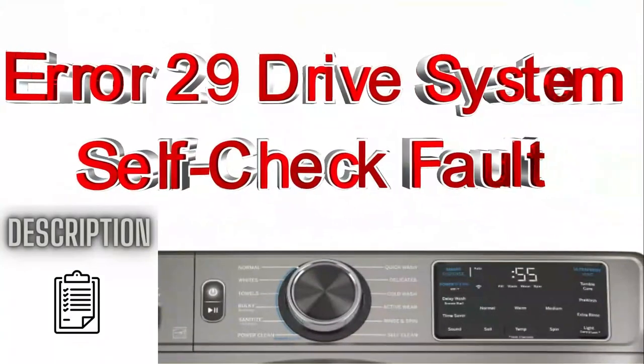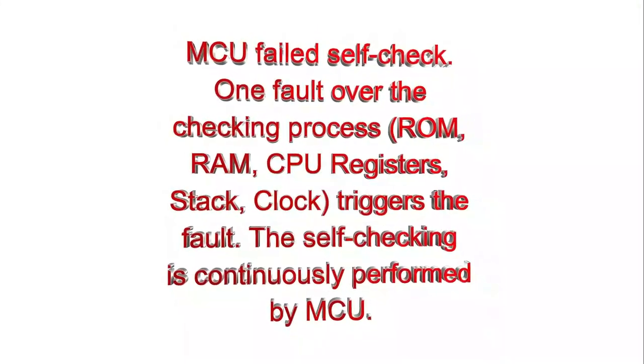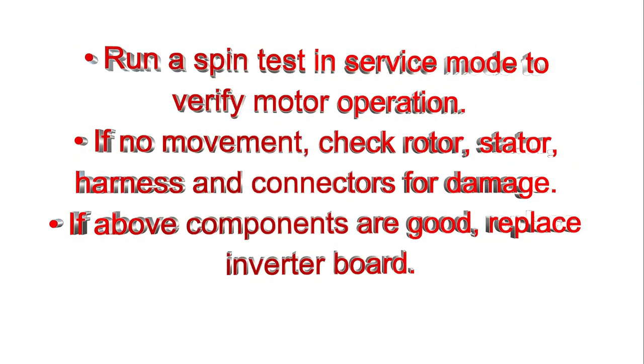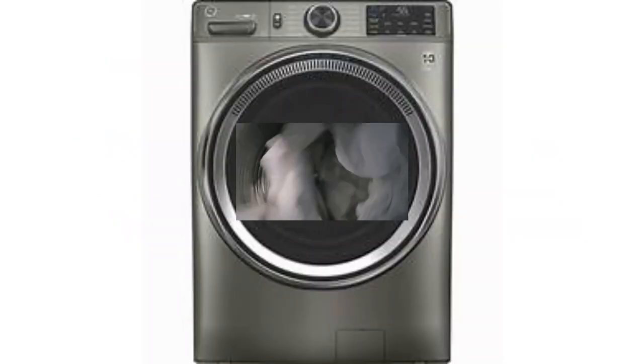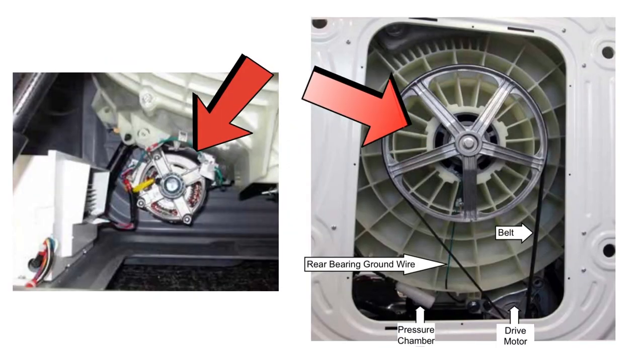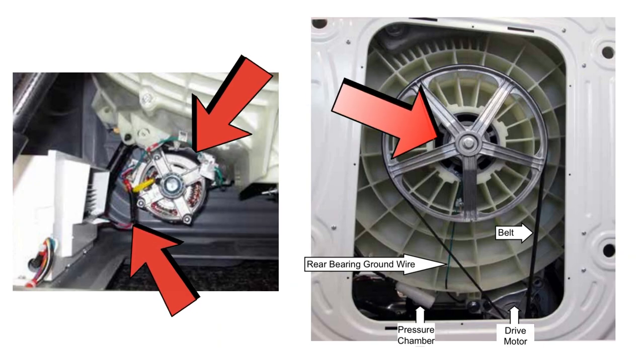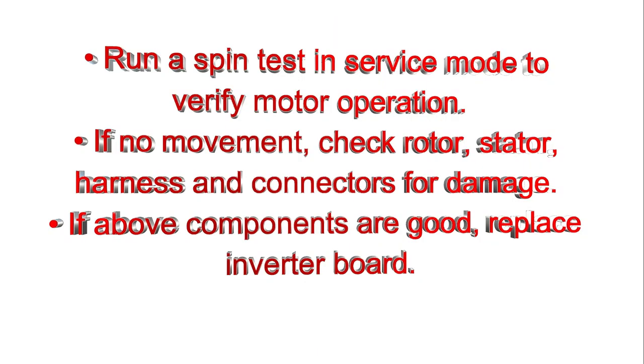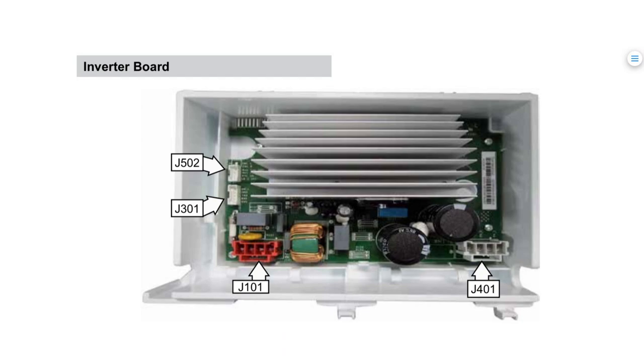Error 29, drive system self-check fault. MCU failed self-check. One fault over the checking process, ROM, RAM, CPU registers, stack, clock, triggers the fault. The self-checking is continuously performed by MCU. Run a spin test in service mode to verify motor operation. If no movement, check rotor, stator, harness, and connectors for damage. If above components are good, replace inverter board.